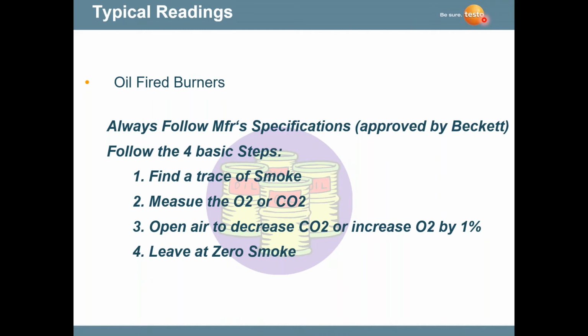Then from there, you measure oxygen or CO2. What you're trying to do is find a trace of smoke at 1, and you measure the oxygen at that point using a combustion analyzer. Then you open up the air shutter, and when you do that, you're going to increase the air by 1%. This is going to leave you at a very good combustion efficiency and also at a 0 smoke.